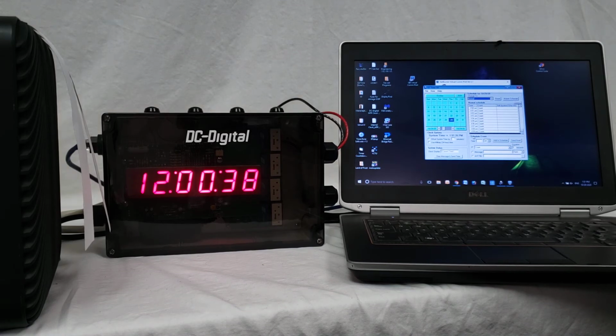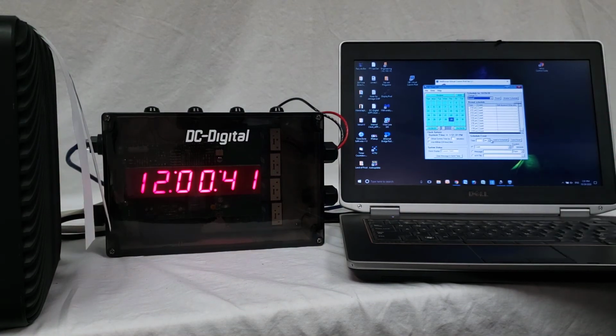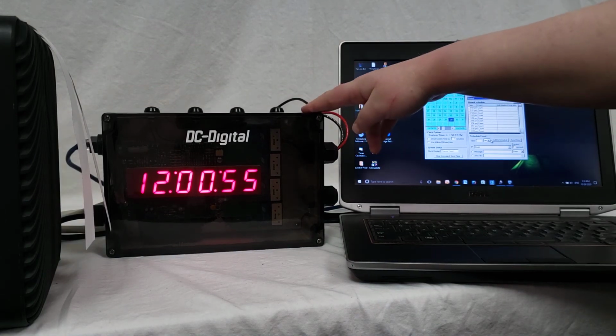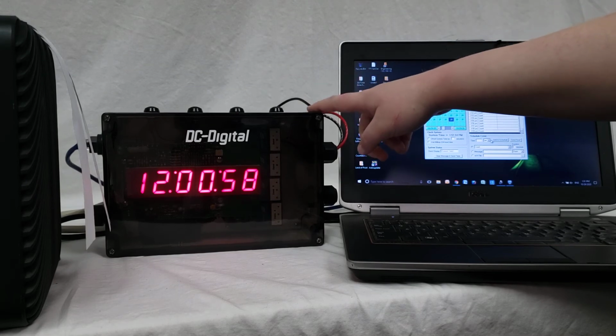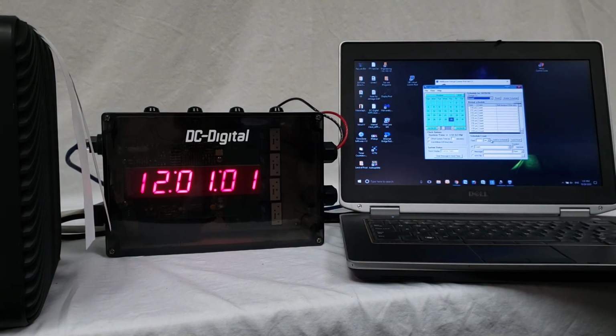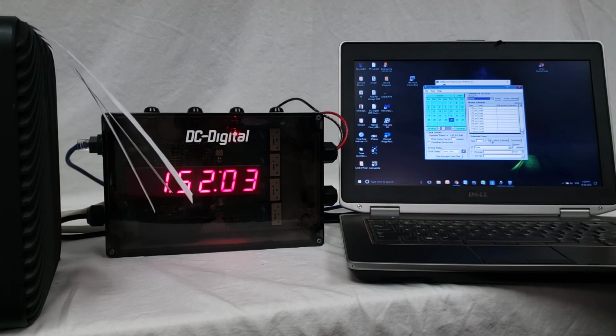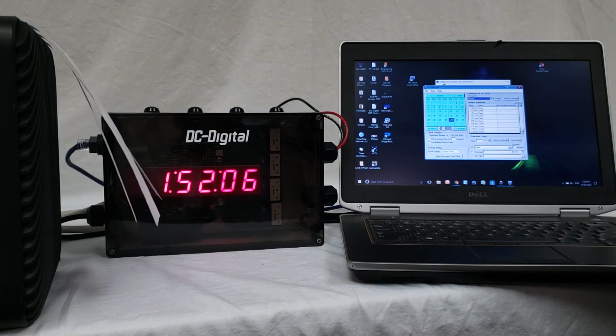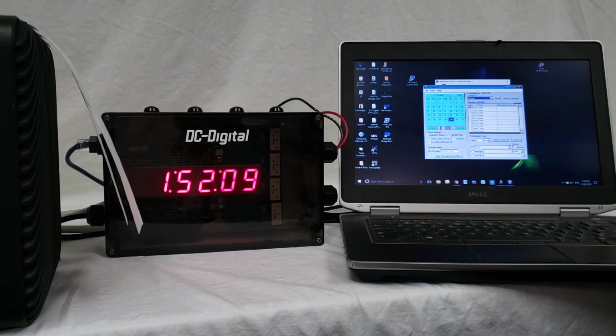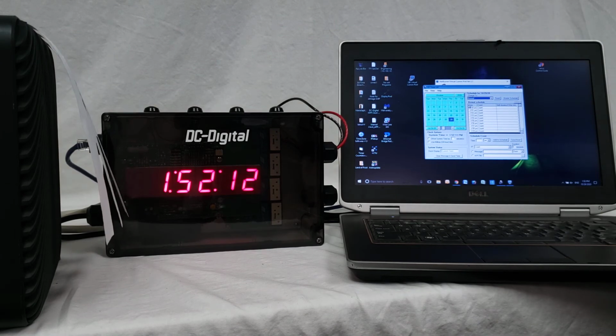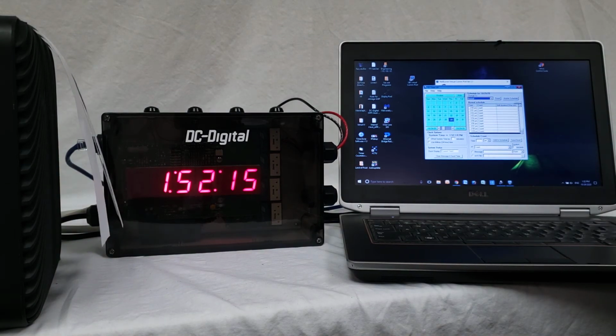And the way that the update works with EasyTime is that EasyTime will send out data every 10 seconds. So on the minute, and then 10 seconds, 20 seconds, it'll send out data. So because this takes 1 minute to update, it will receive the first 10-second pulse from EasyTime after it reaches 12:01. And there we go. So it connected, it updated from EasyTime, the relays turned on, and it is now showing the correct time.